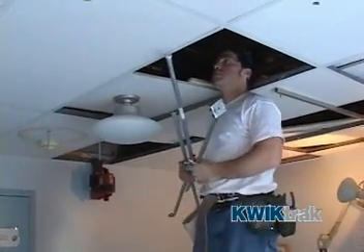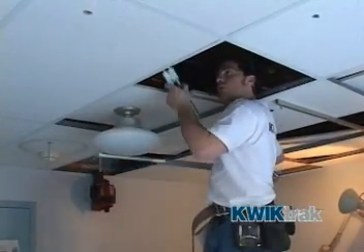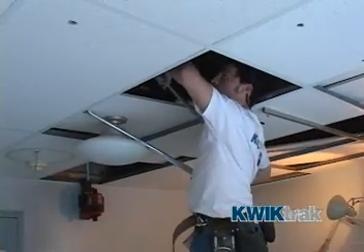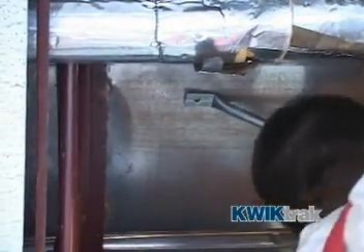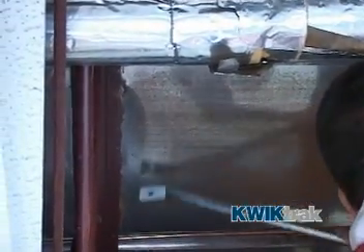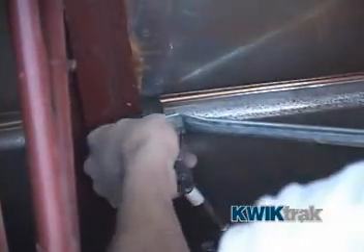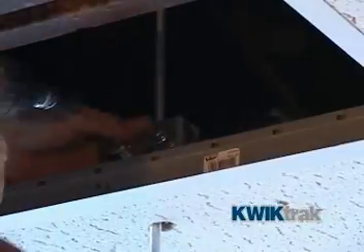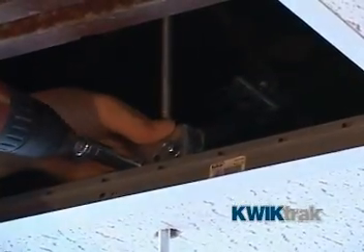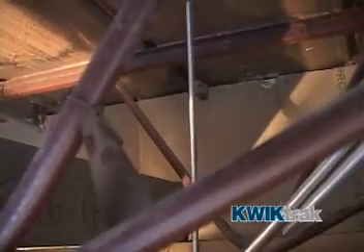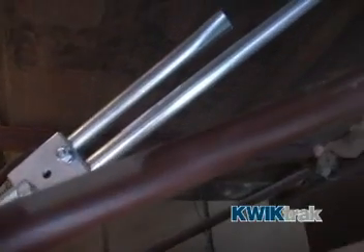Where the distance from the ceiling anchor structure, rod anchor point, to the drop ceiling, rod exit point, exceeds 305 millimeters, a lateral support may be required. The support is attached to the ceiling structure or anchored to the deck and laterally dropped to the exit point of the threaded rod, where a connection is made to the threaded rod at the suspended ceiling point. Once installed, the anchored threaded rod, in combination with two lateral support connection points, forms a solid anti-sway device.